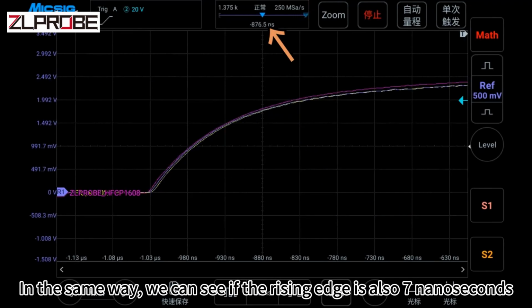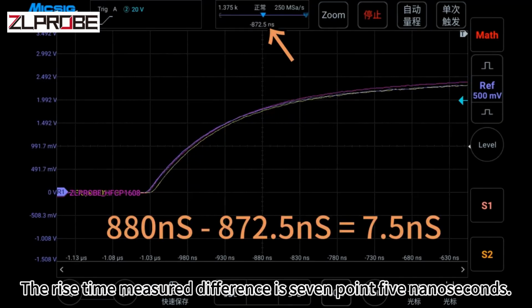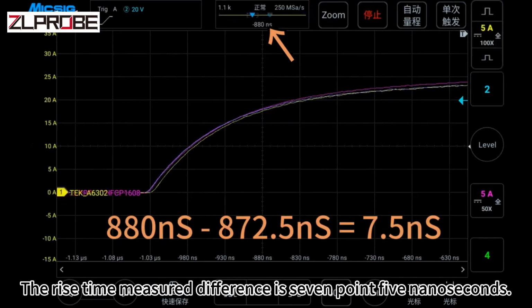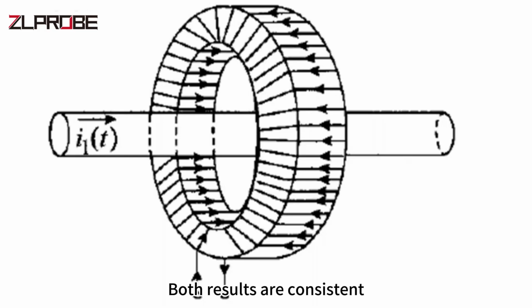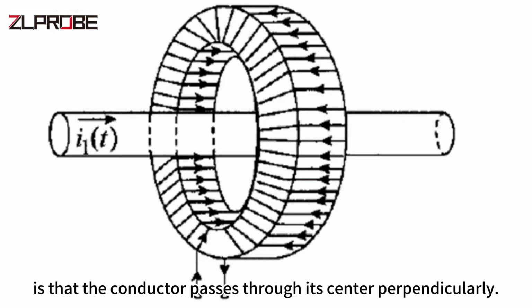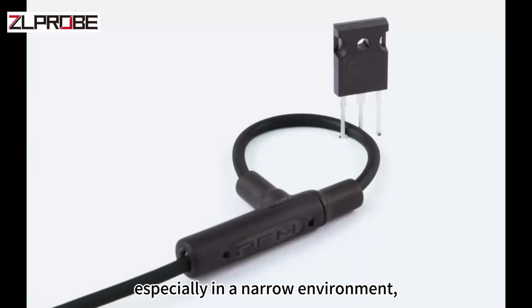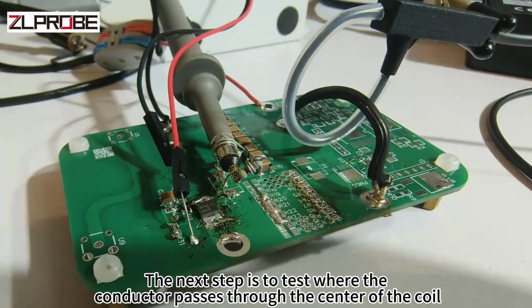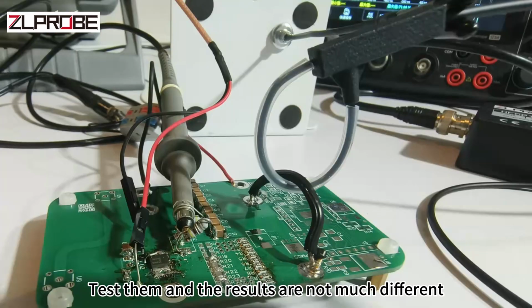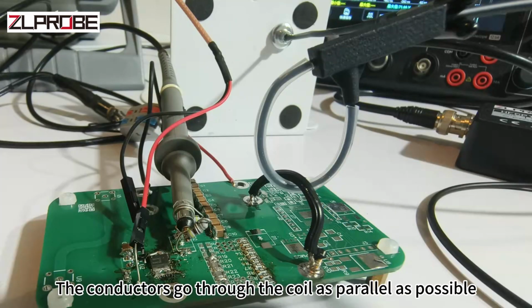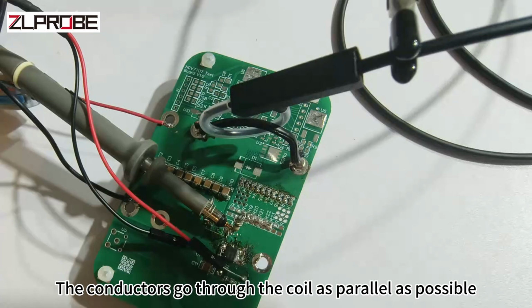In the same way, we can see if the rising edge is also 7 nanoseconds. The rise time measured difference is 7.5 nanoseconds. Both results are consistent. For the Rogowski coil, the recommended ideal test orientation is that the conductor passes through its center perpendicularly. Especially in a narrow environment, we often fail to meet this optimal position. The next step is to test where the conductor passes through the center of the coil and the edge position. Test them and the results are not much different. The conductors go through the coil as parallel as possible.